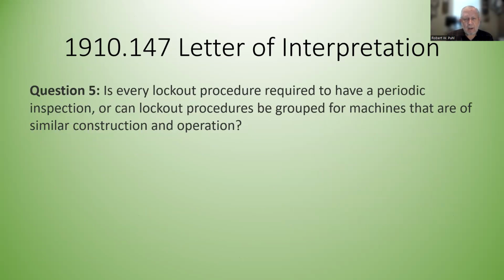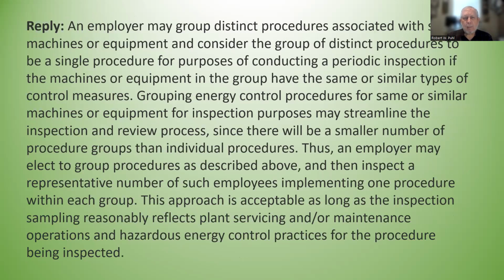Question 5, is every lockout procedure required to have a periodic inspection, or can lockout procedures be grouped for machines that are of similar construction and operation? This is an interesting one too, one you might run up against. Reply: an employer may group distinct procedures associated with similar machines or equipment and consider the group of distinct procedures to be a single procedure for purposes of conducting a periodic inspection if the machines or equipment in the group have the same or similar types of control measures.